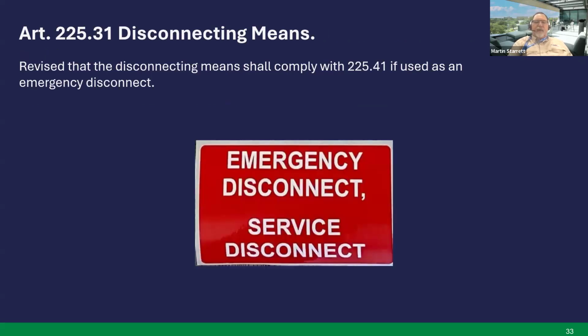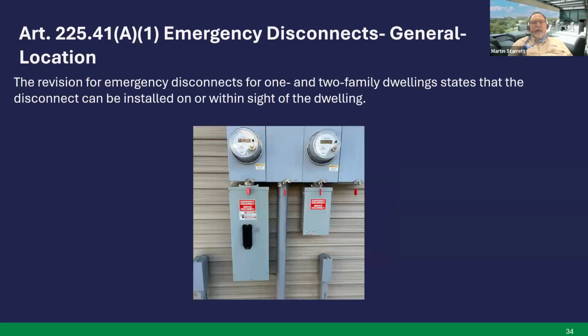Article 225.31, disconnecting means. Revised so that the disconnecting means shall comply with 225.41 if used as an emergency disconnect. Next, 225.41(A)(1), emergency disconnects, general location. The revision for emergency disconnects for 1 and 2 family dwellings states that the disconnect can be installed on or within sight of the dwelling.